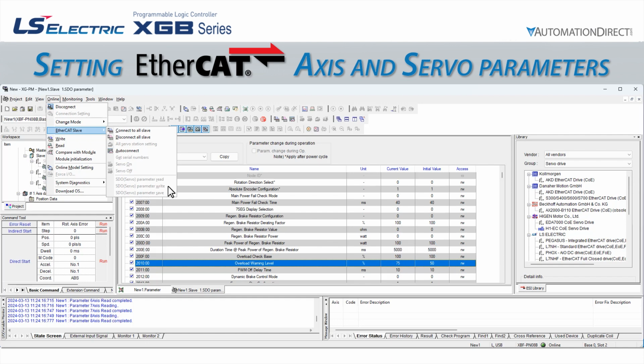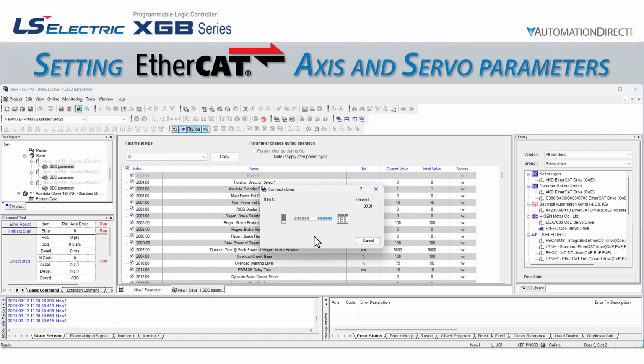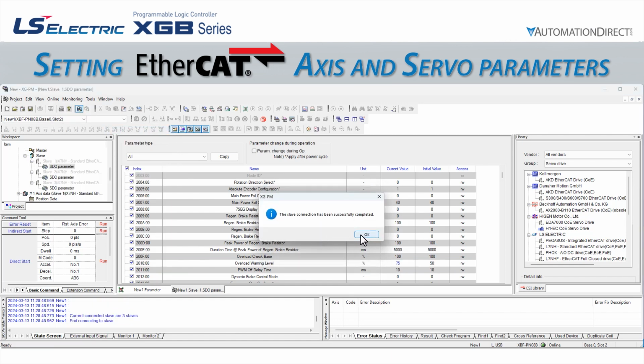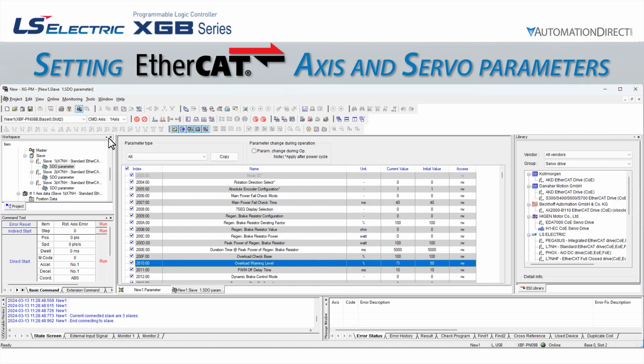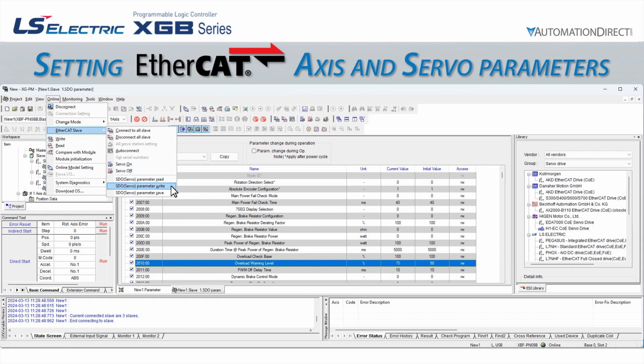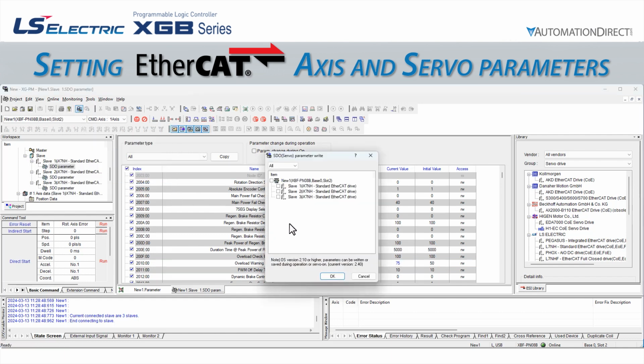We first must select Connect to All Slave and wait for the software to run through the connection process. Once it gives us the confirmation it connected successfully, we can now go back and access the SDO servo parameter write function. This will open the SDO servo parameter write pop-up window, and here we can select which drives we will write to. We could write to just the drive we altered, which would be the slave 1 drive. However, I find it's easier to not accidentally miss parameter changes if I just go ahead and write to all the drives each time I do this step.